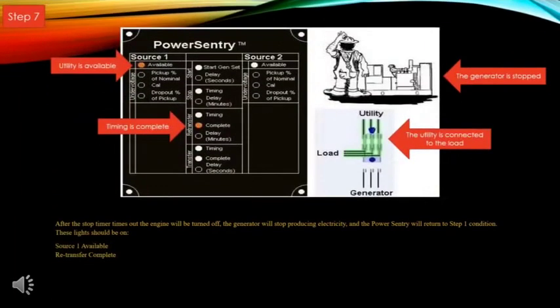Step seven: after the stop timer times out, the engine will be turned off. The generator will stop producing electricity and the power sentry will return to step one condition. The source one available light is on, the generator is not running, the retransfer timing light has gone to complete, and the utility is connected to the load via the green contactors. Now you're ready for another power outage.